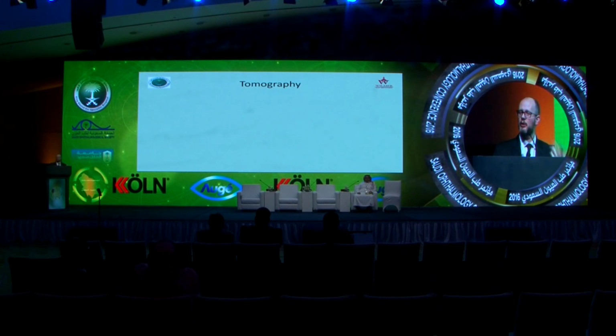And that's essentially what the tomographers do, is instead of mapping the surface with rings like the topographers do, it takes a slit beam, just like you do with the slit lamp in the microscope, and then measures the thickness of that slit beam and tells you the relative curvature and thickness of the cornea at each point where it takes an image. The Orbscan takes one slit and slides it across the cornea, taking images as it goes across, and then manufactures a 3D reconstruction of that.